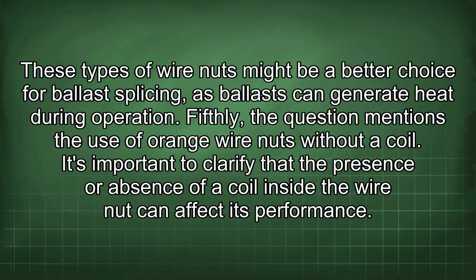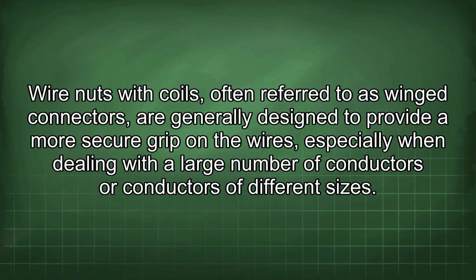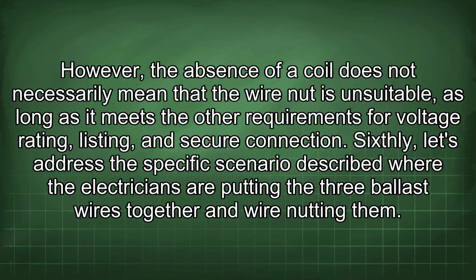Fifthly, the question mentions the use of orange wire nuts without a coil. It's important to clarify that the presence or absence of a coil inside the wire nut can affect its performance. Wire nuts with coils, often referred to as winged connectors, are generally designed to provide a more secure grip on the wires, especially when dealing with a large number of conductors or conductors of different sizes. However, the absence of a coil does not necessarily mean that the wire nut is unsuitable, as long as it meets the other requirements for voltage rating, listing, and secure connection.